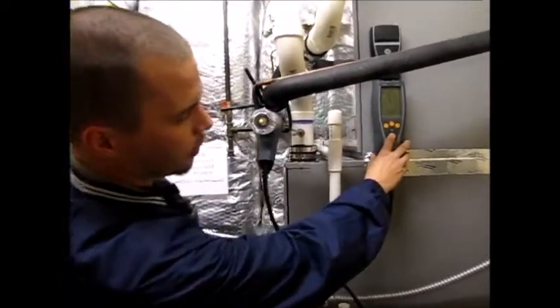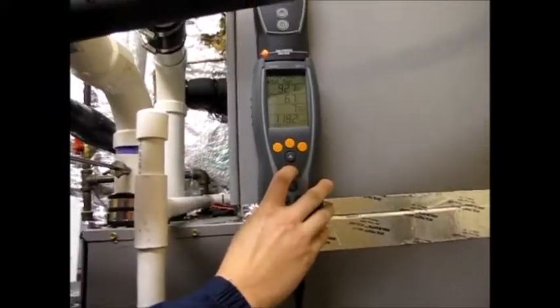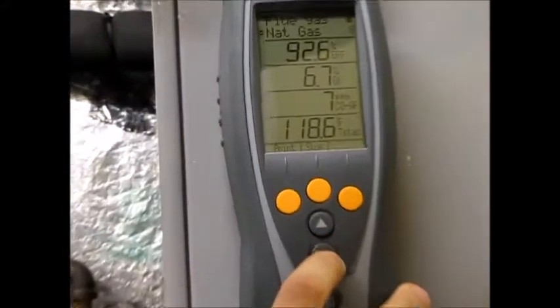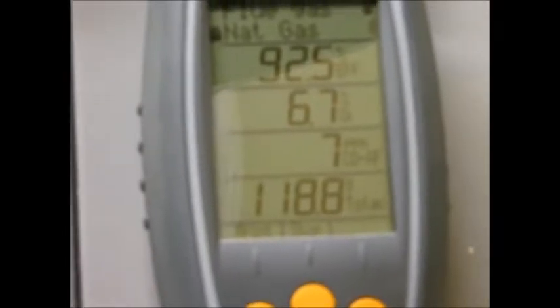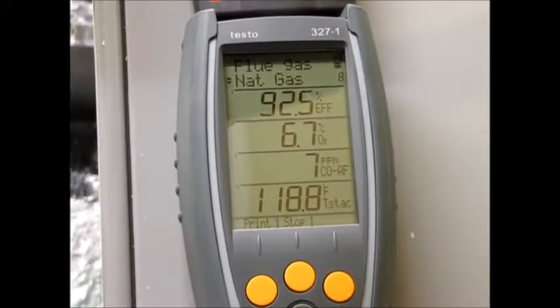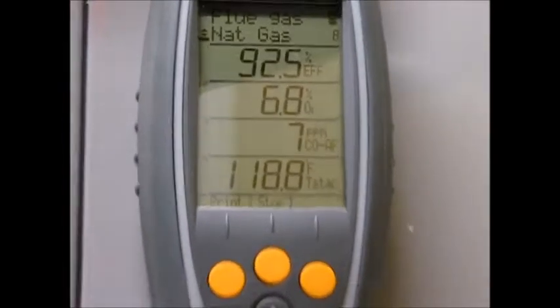If we scroll through real quick, it's showing that we're 92.7, 93% efficiency. We've got a 6.7 oxygen percentage, which our allowable values are between 5 and 7. We're definitely doing great on our actual parts per million of CO. We're well under 100, which is where we need to be.